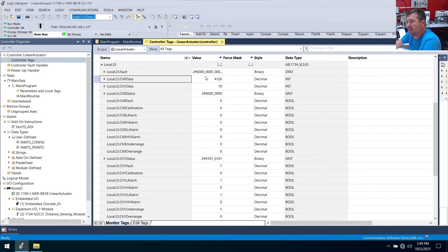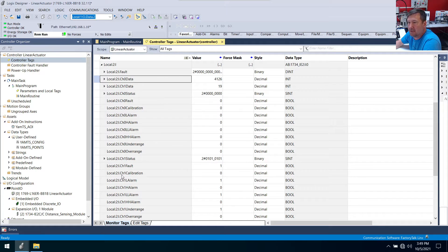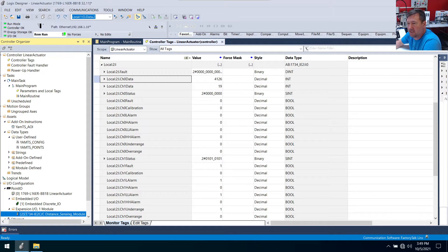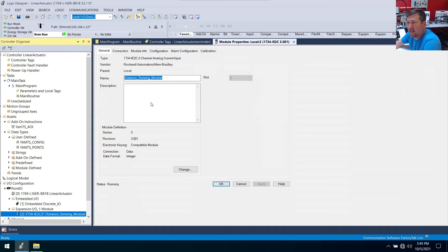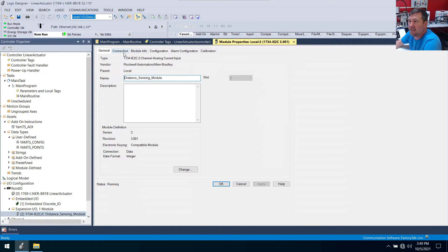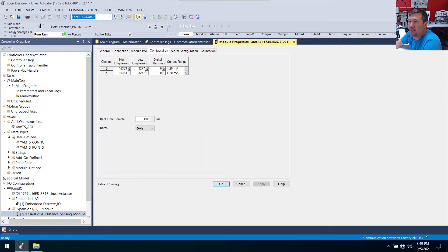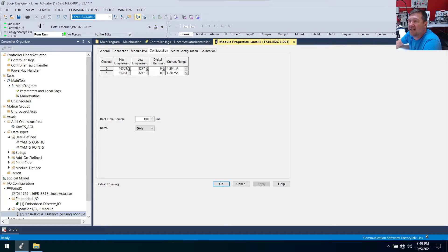Okay, no doubt the analog value is changing as I move it along. Now this actually looks like gibberish. So first let's make sure we understand what these numbers are. If we double click on that expansion module that we just added, the 1734-IE2C, and we go to its configuration, then right here we have a low engineering of 3277. That's 4 milliamp.